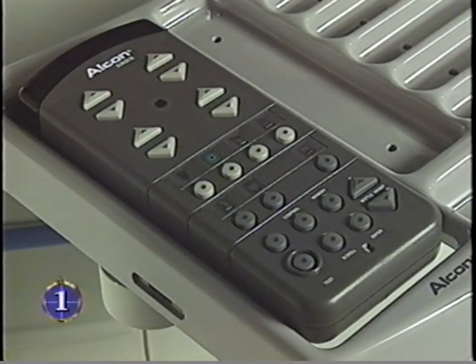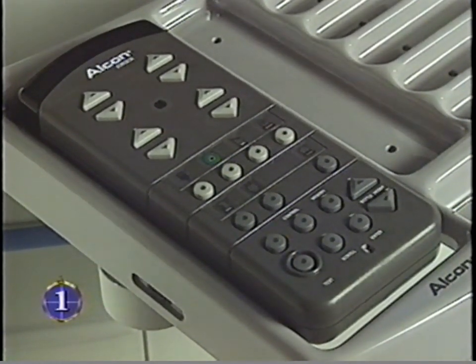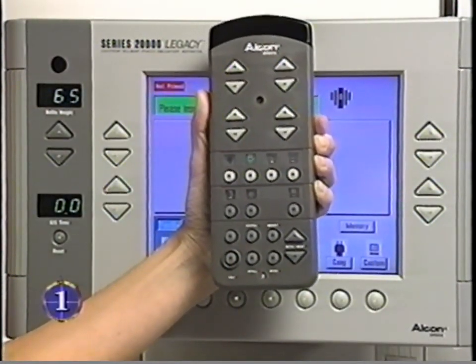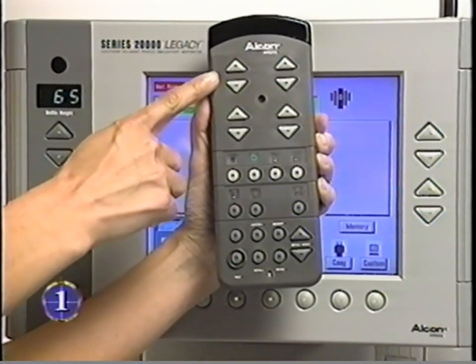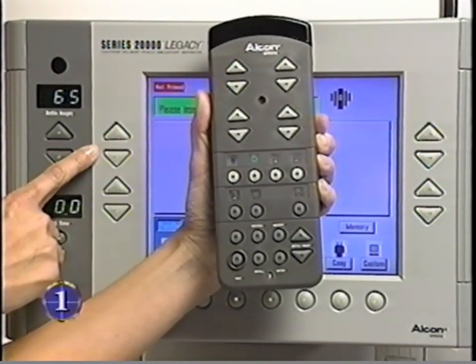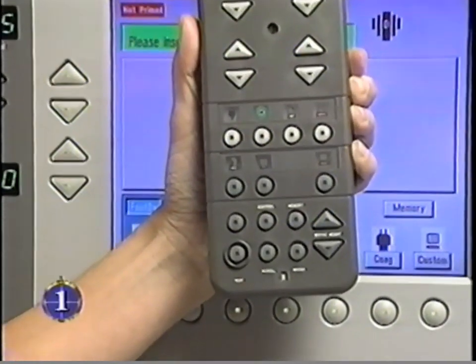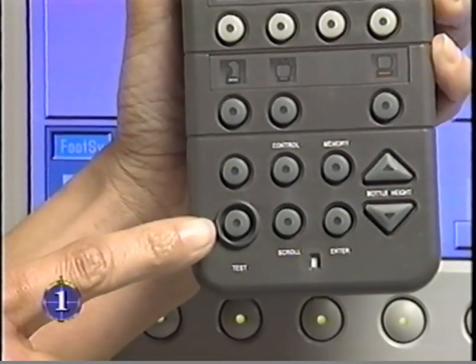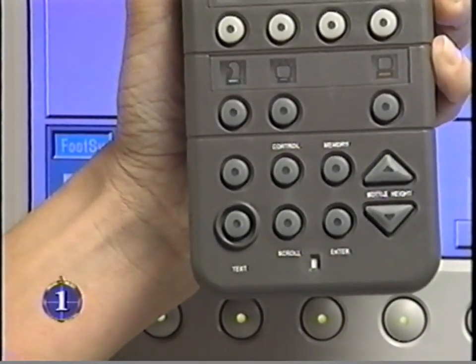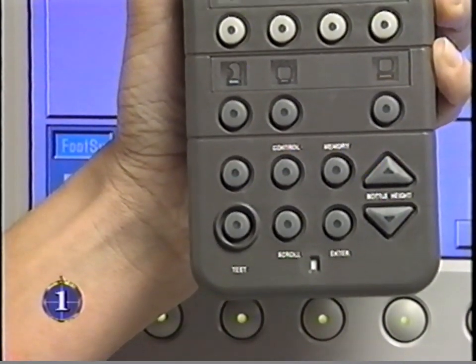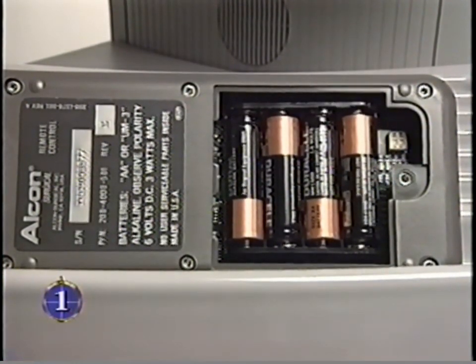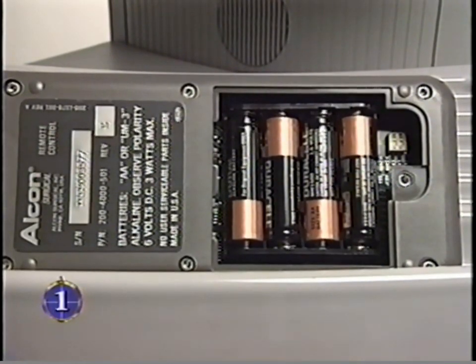Most of the Legacy's functions can be directed from anywhere in the sterile and non-sterile fields using the wireless remote control. The keys and arrows on the remote are arranged much as they are on the Legacy's front panel. All controls are backlit for illumination in low lighting, and the test button has a raised collar to prevent accidental activation. The remote and the Legacy unit must be set to operate on the same channel.